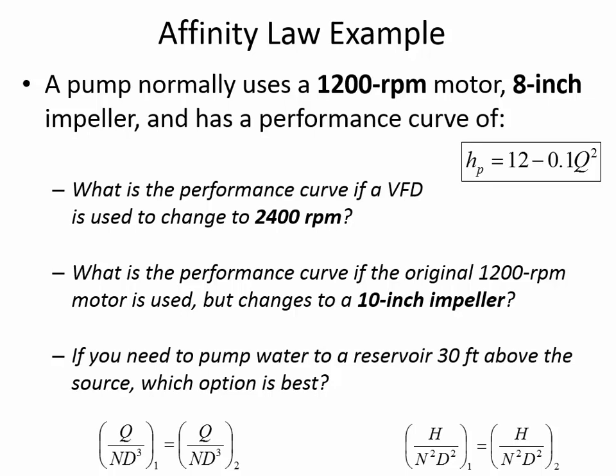We do a similar thing if we are going to keep it at 1200 RPM, but we want to switch to a 10-inch impeller. So now we'll just say, for the diameter, D1 originally was 8-inch, and we want D2 to be 10-inch, but everything else stays the same in this second bullet point here. So what is the pump curve going to look like?